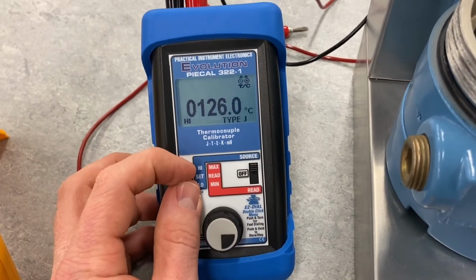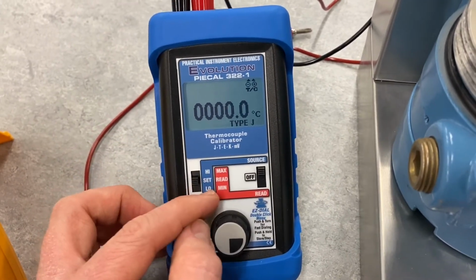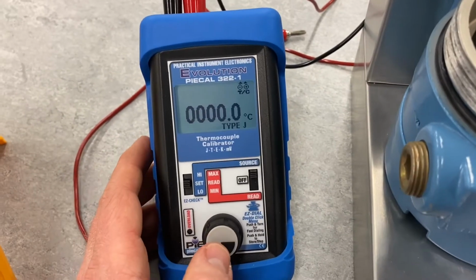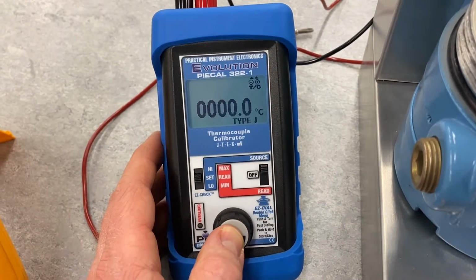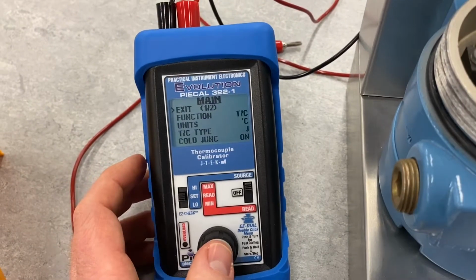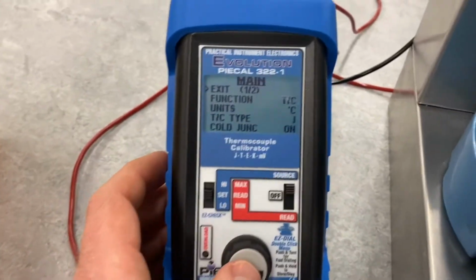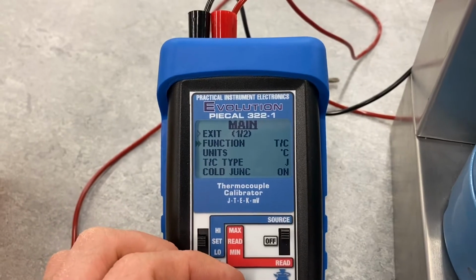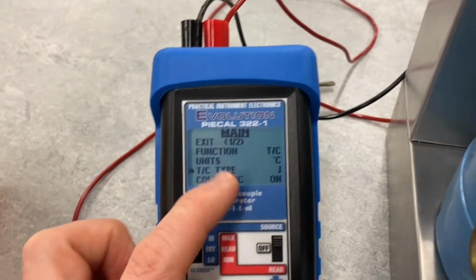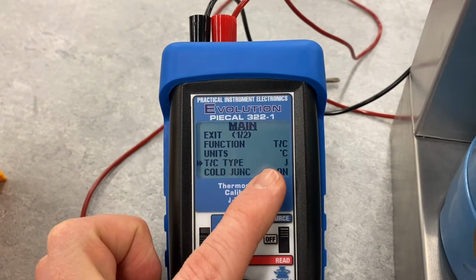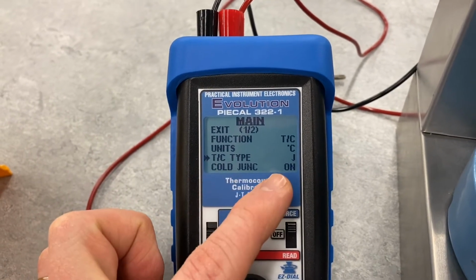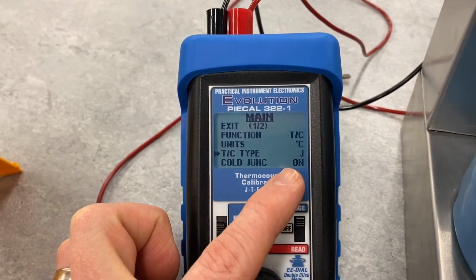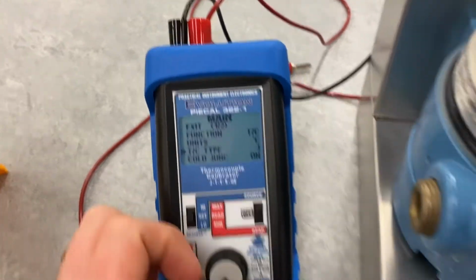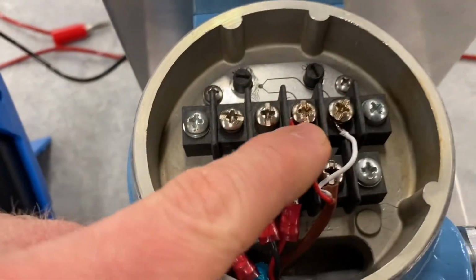To do that, we'll go back to the middle switch here, press this button once. Yeah, double, we have to press it 2 times, and then now we can make changes here. We can change the units, we can change the type of thermocouple, that needs to be set for type J, and we also want to have the cold junction compensation set on here. And what that does is it measures the ambient room temperature, because the thermocouple has a reference junction right here, and then also at the end here, the measure junction.